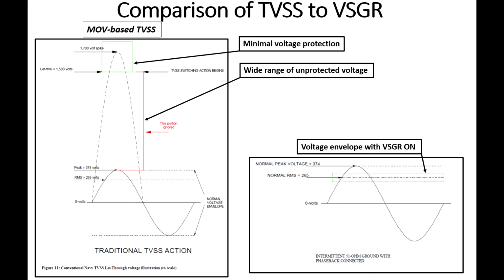Here's a very good graphical representation of what a MOV-based TVSS does compared to controlling the voltage with a voltage stabilizing ground reference. On the left, we see a graphic that we got from the Department of Defense showing the significantly high amount of unprotected or ignored area of a voltage spike. As the voltage gets to the switching threshold, in this case on a 450 volt power system, the MOV would start conducting at around 1500 volts. So there's a very small amount of protection at the top, and a very large unprotected area below that.